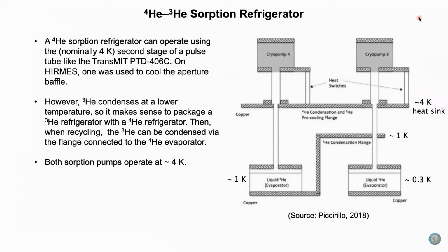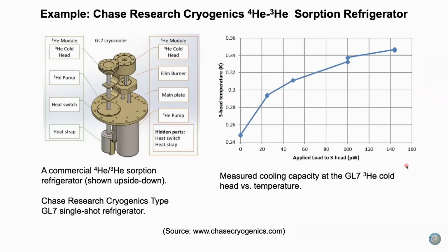Now, going to helium-3, I mentioned this before, helium-3 does not condense at 4 Kelvin. So you can't quite do the same thing unless you've got a 3 Kelvin heat sink, which you usually don't. So in this case, it makes sense to package a helium-3 sorption refrigerator with a helium-4 sorption refrigerator. And the main purpose of the helium-4 sorption refrigerator is to provide cooling at this condensation flange, about 1 Kelvin. So as you're recycling this cryopump here, this sorption pump, the helium-3 will come down this tube and get to this point and condense. So you get liquid helium-3 in the evaporator. And you can run it down to 0.3 Kelvin or below.